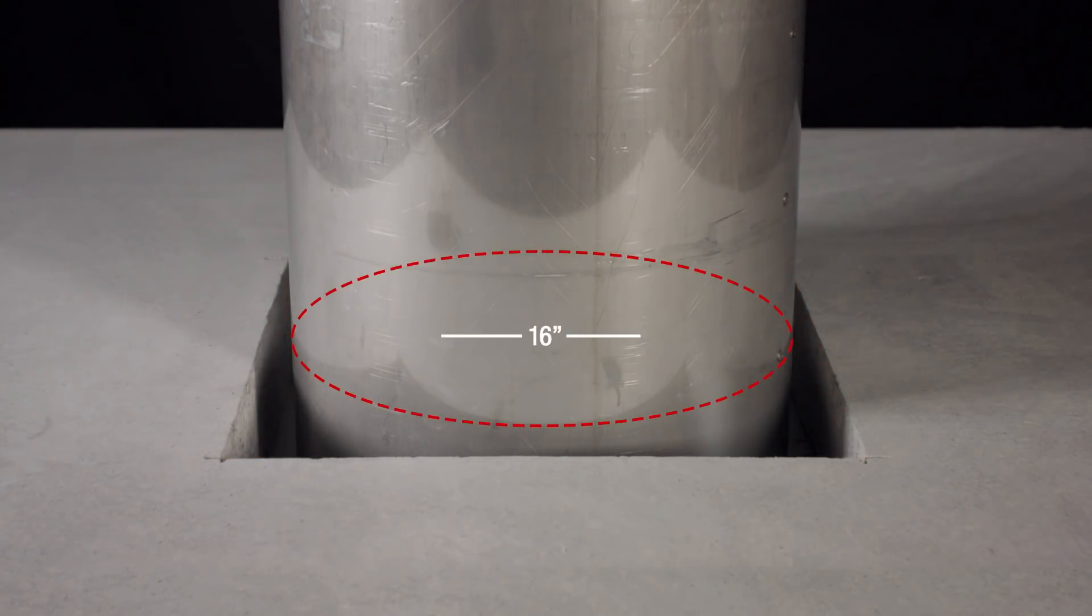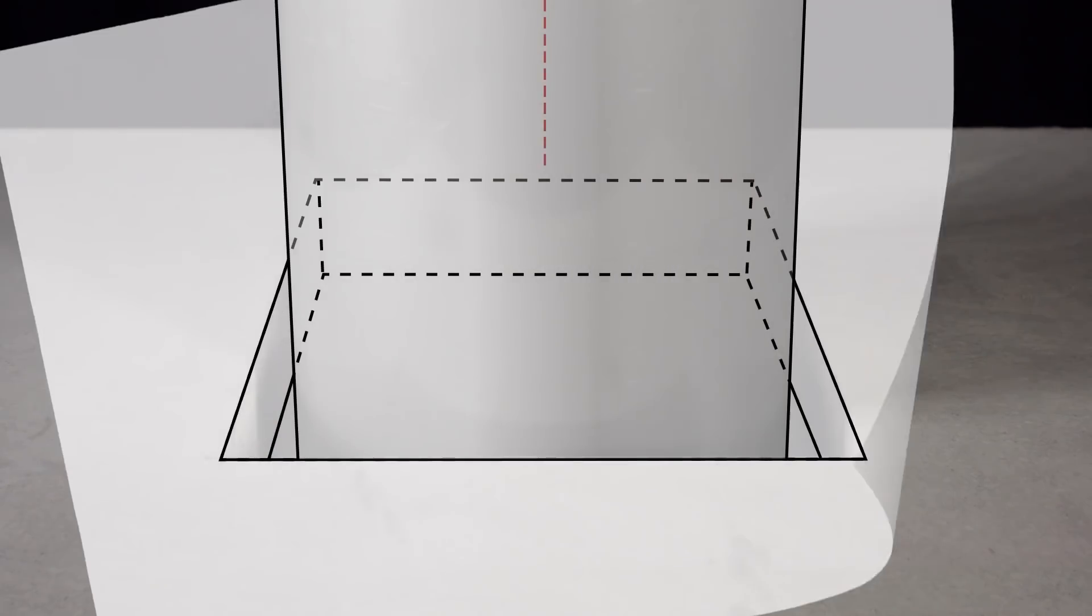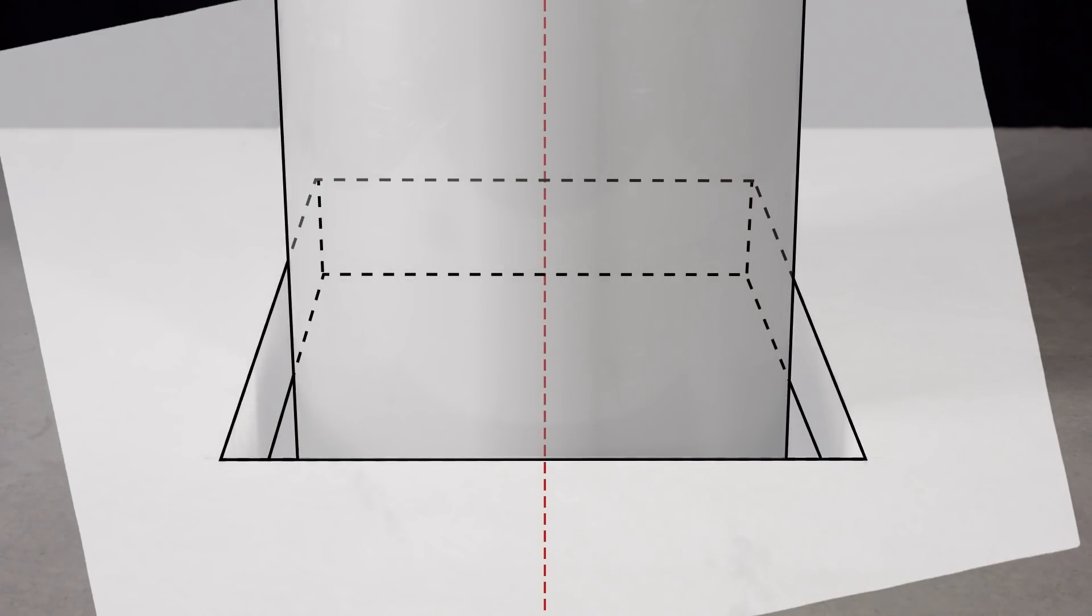For example, the duct shown here has an outer diameter of 16 inches, so the opening in the floor or ceiling is an 18 to 19 inch square. Once this is confirmed, you can center a section of duct through the floor or ceiling.